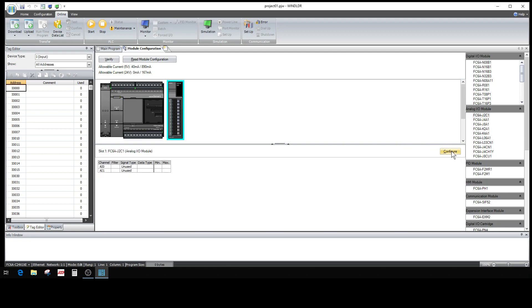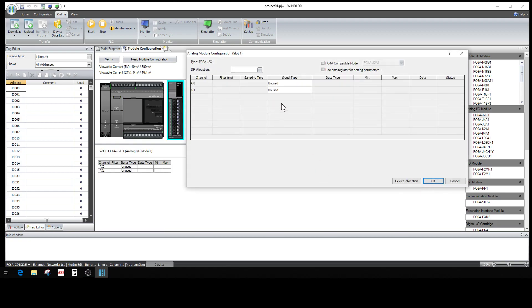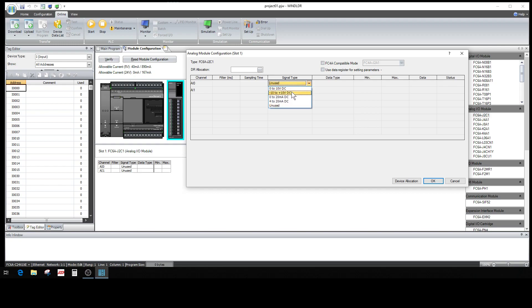While that's highlighted, click Configure. This is Analog One — that was a two-point card, so it only has two points: zero and one. You have to pick your signal type. This is where you can pick between zero to ten, minus ten to plus ten, zero to twenty, or four to twenty. Four to twenty is what I use a lot.